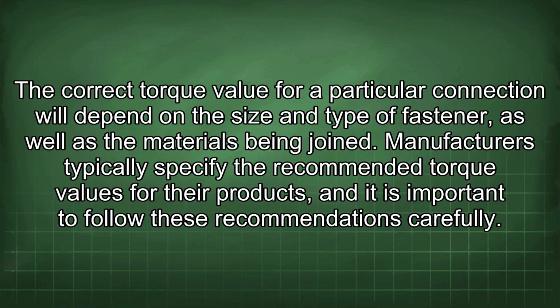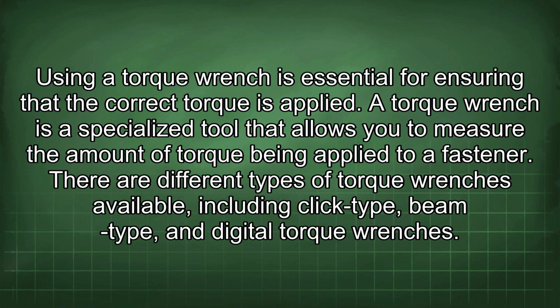The correct torque value for a particular connection will depend on the size and type of fastener, as well as the materials being joined. Manufacturers typically specify the recommended torque values for their products, and it is important to follow these recommendations carefully. Using a torque wrench is essential for ensuring that the correct torque is applied. A torque wrench is a specialized tool that allows you to measure the amount of torque being applied to a fastener. There are different types of torque wrenches available, including click type, beam type, and digital torque wrenches.